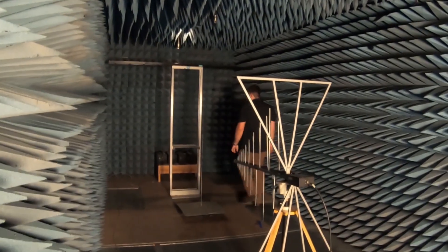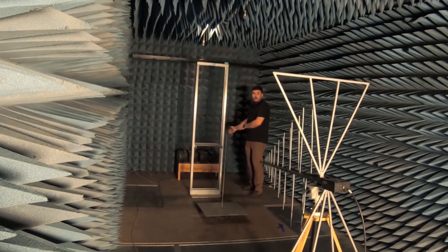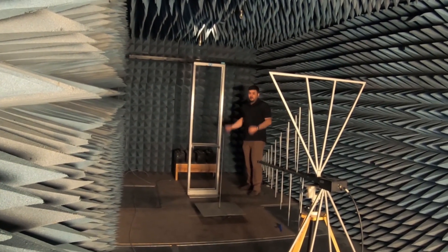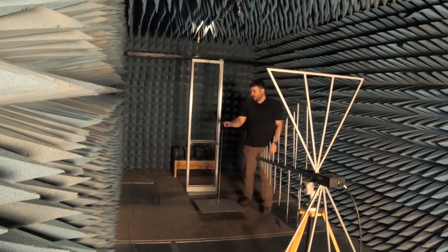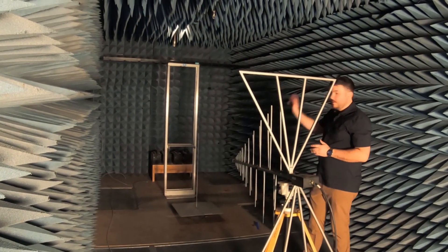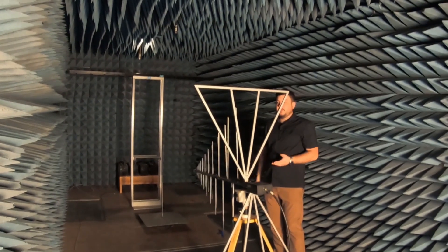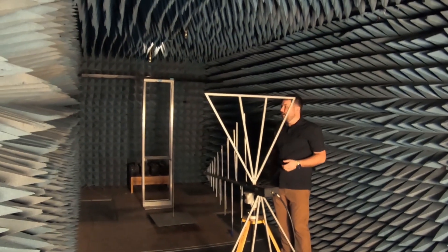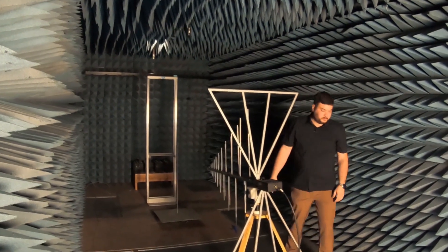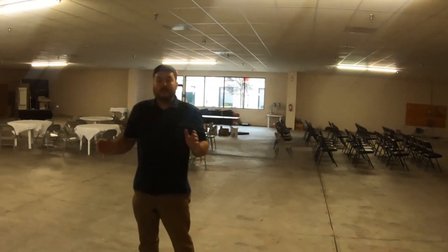When it's time to test a piece of equipment, we load it onto this rack, then power it with boat batteries so there's no outside power grid interference, and we use two antennae to measure. We have an omnidirectional antenna here, and then this antenna is focused directly on the unit under test. Right through the wall, we have a console where we can monitor on the oscilloscope to see what's going on as we perform various tests. That concludes engineering — now let's go have a look at production.